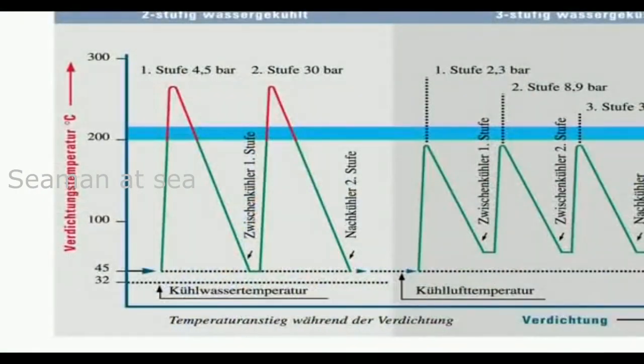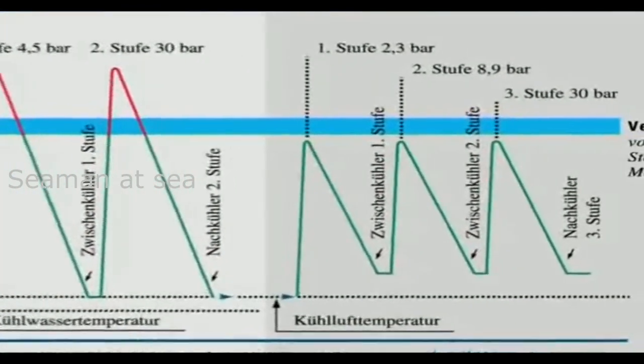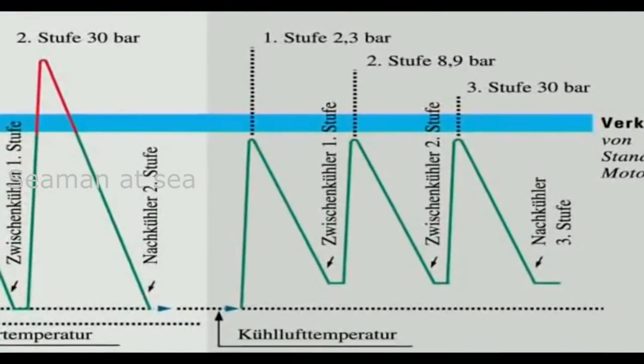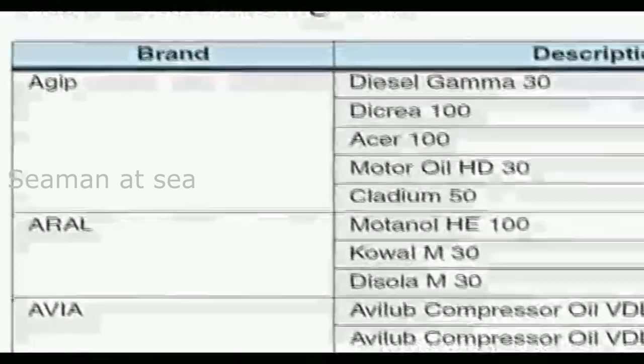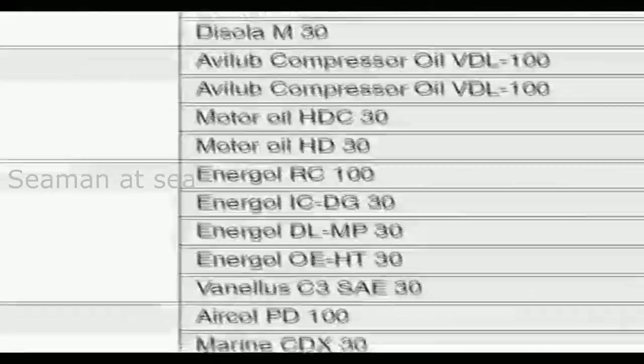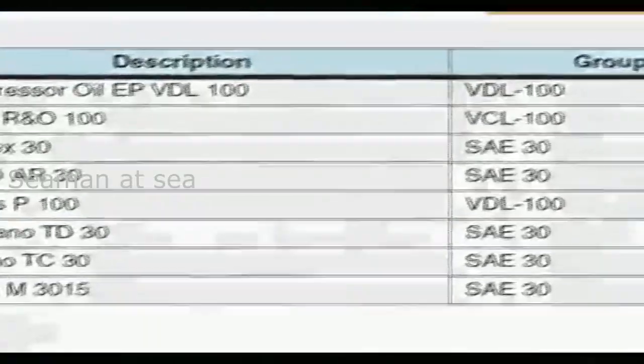The low compression temperatures of three-stage air-cooled compressors lower the risk of carbonization on valves, even when mineral oils are used. Sauer recommends the use of normal SAE 30 oils, as they are also used in diesel engines and readily available.